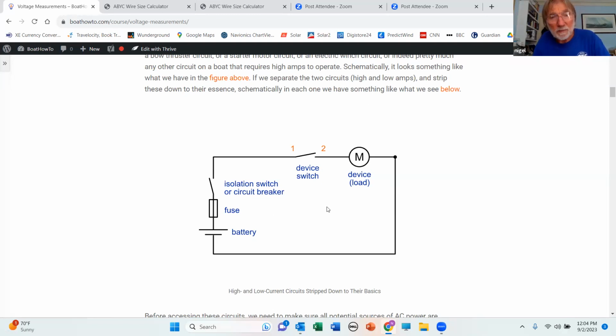Sorry, let me change this. We put the meter lead in place. This is a circuit that we can energize, but it's not performing properly, so we can load it up. We put the meter lead on battery positive. We go to the positive terminal on the device. We've established that we're losing 3.6 volts. We took a reading across the battery and then we took a reading at the load. So we go from here to here and we measure the voltage.